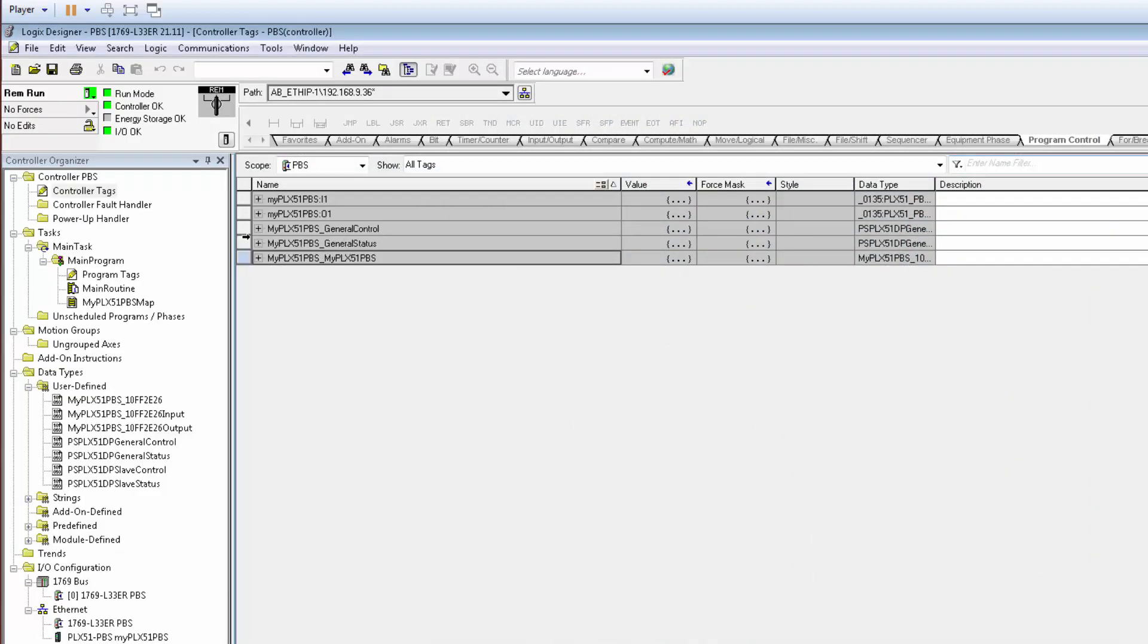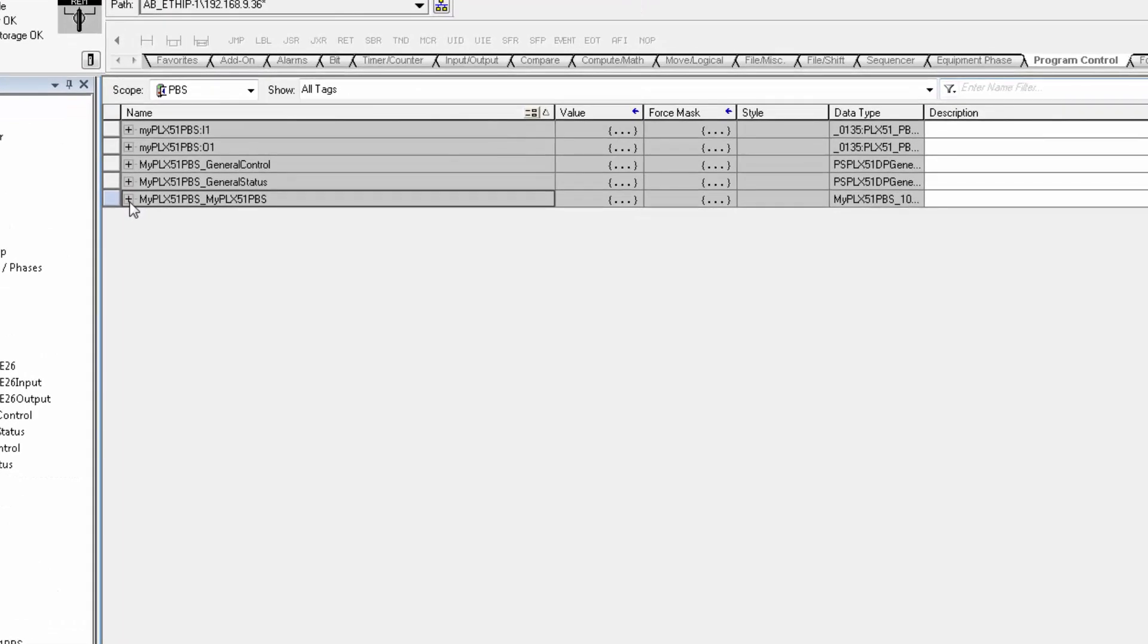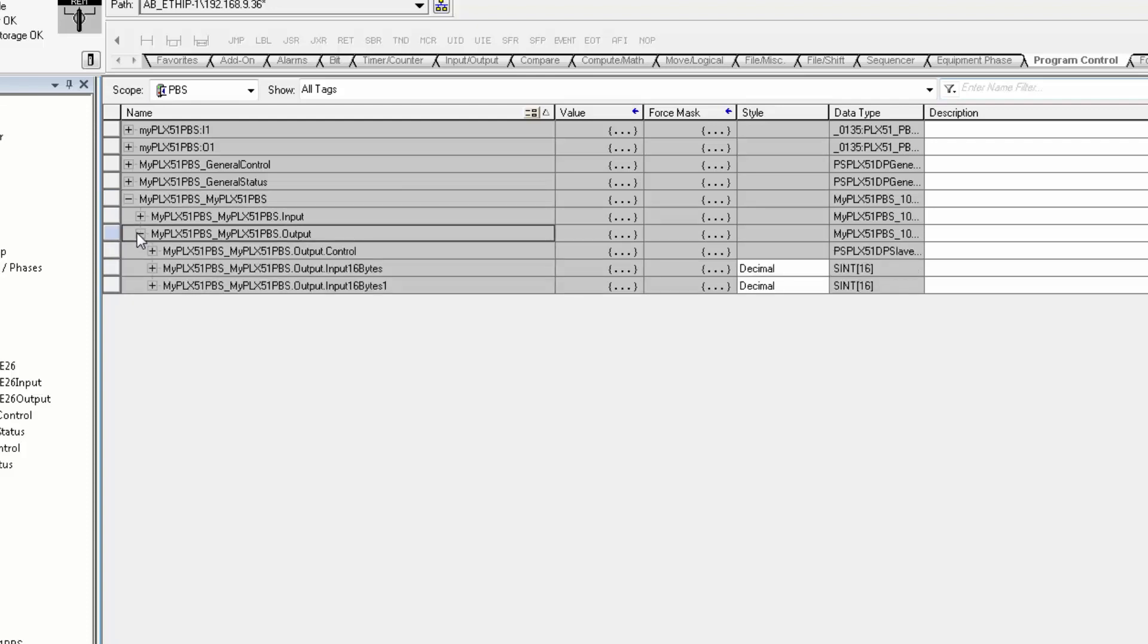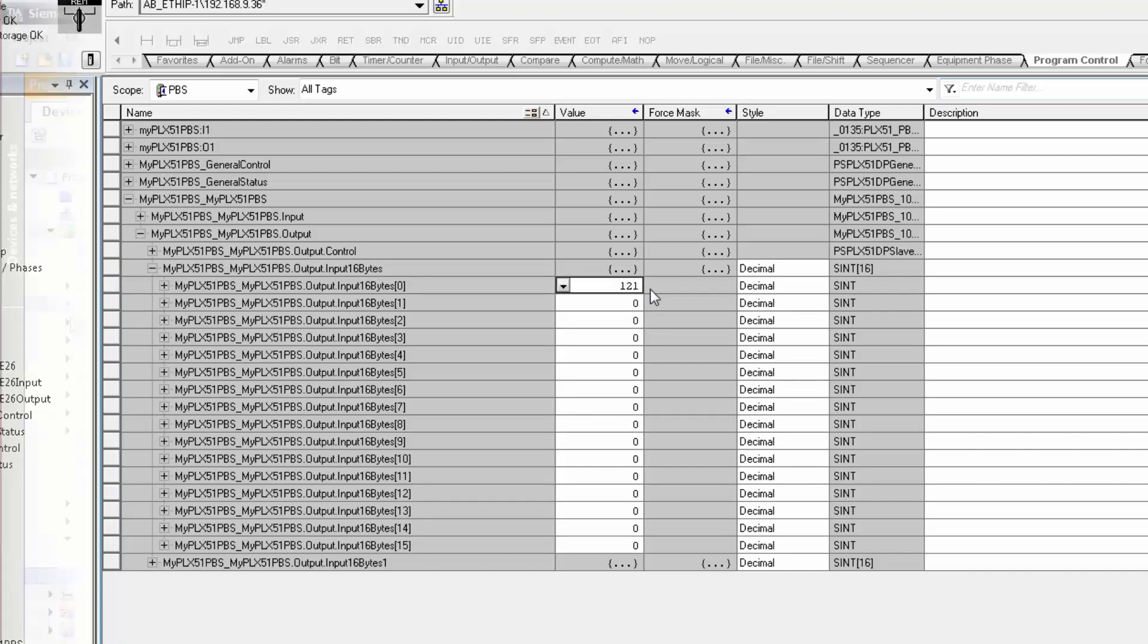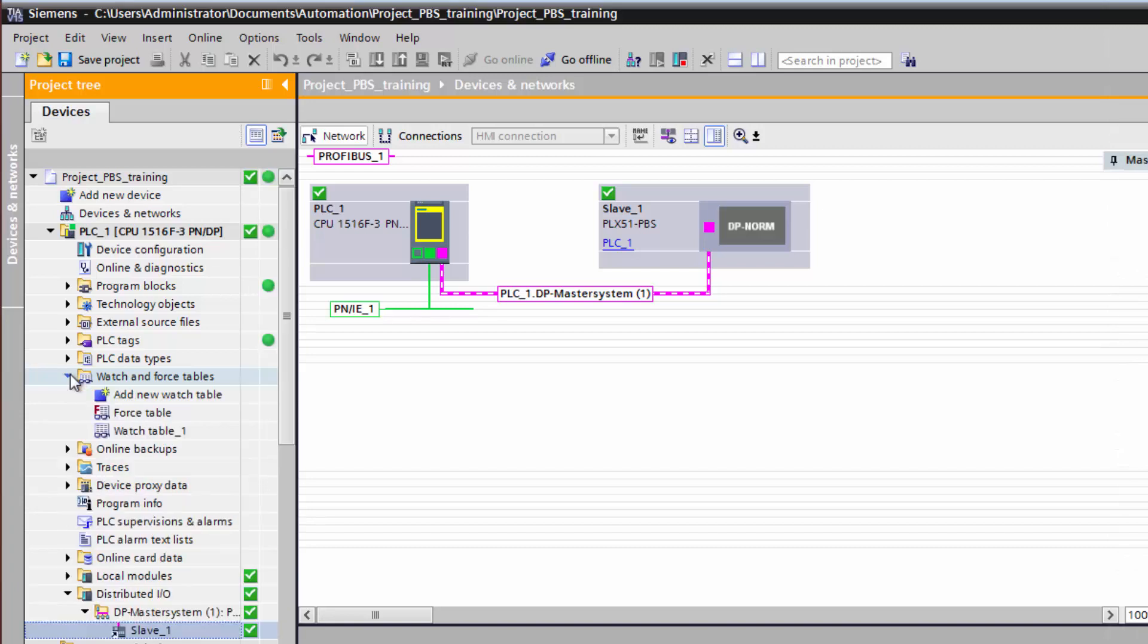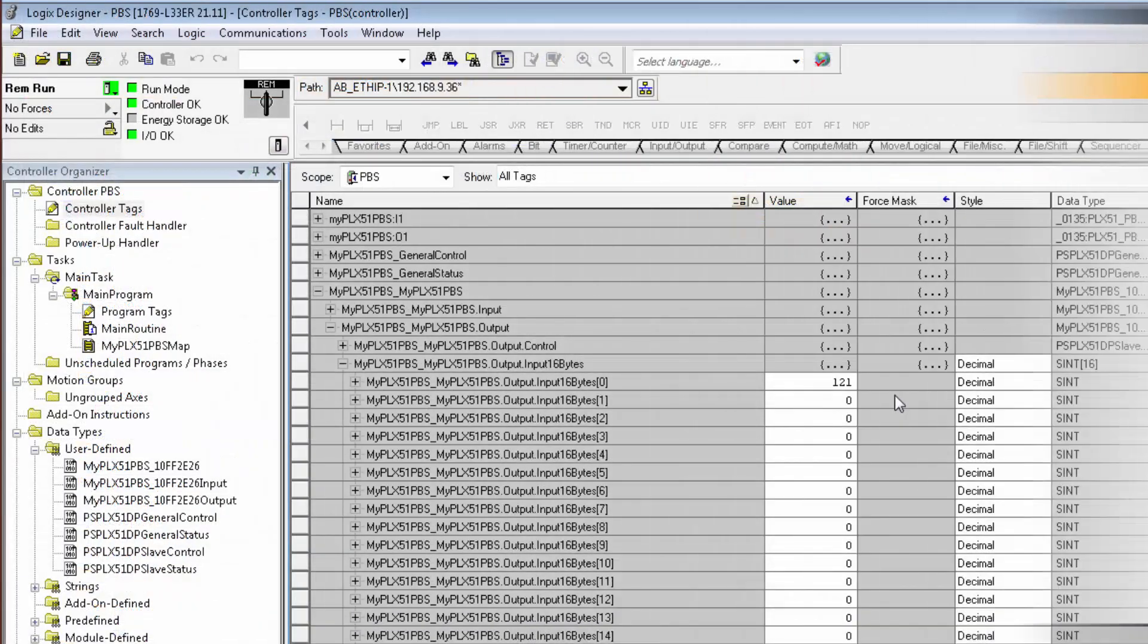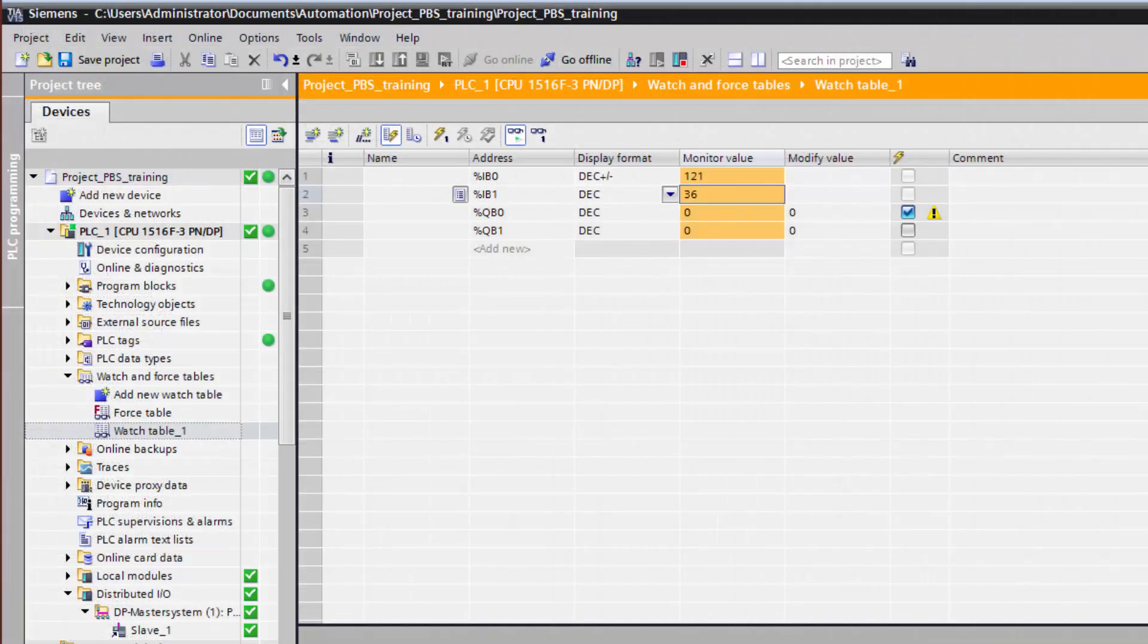Finally, we'll return to Studio 5000 and take a look at the tags. You can see an entry for the PLX51 PBS, My PLX51 PBS, Input and Output. Now, the exact name here will depend on the name that you use. Now, the input and output tag labeling here is a little unusual. Under Output, you find Output.Input. This is the CompactLogix output data that will be the input data for the S7 master on the PROFIBUS side. So the output input tags will represent data that our S7 master receives from the CompactLogix through the PROFIBUS port on the PLX51 gateway, which it will regard as a slave. So you can see, if I enter a value in the tags here, it will appear as input data to my S7.